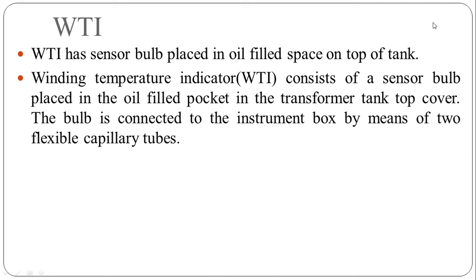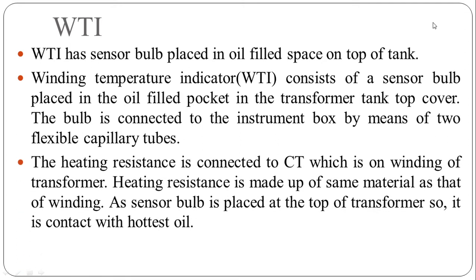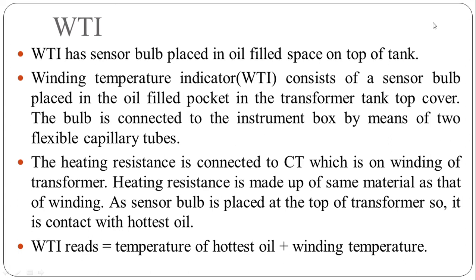The bulb is connected to the instrument box by means of two flexible capillary tubes. The heating resistance is connected to CT which is on winding of transformer. Heating resistance is made up of same material as that of winding. A sensor bulb is placed at the top of transformer so it is in contact with hottest oil in the transformer. The winding temperature indicator reads the temperature of hottest oil and winding temperature.